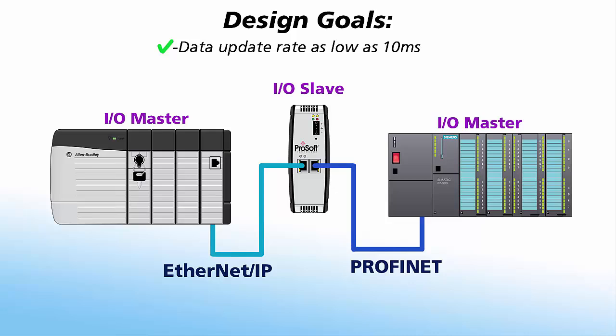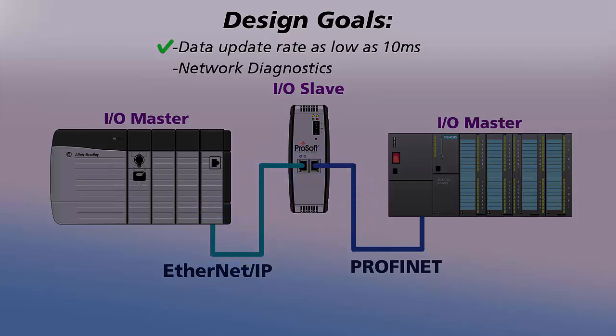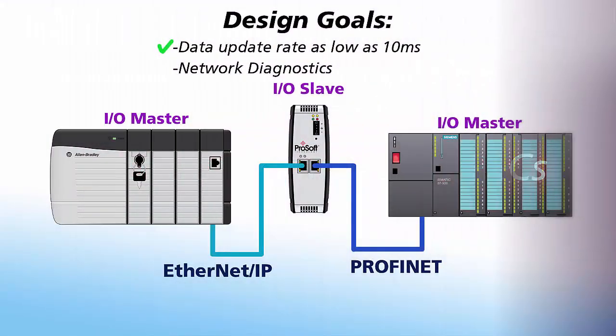We also need to be able to use the PLC programming software, or HMI, to view and troubleshoot communication issues. This method of communication is very deterministic and repeatable, thus offering very fast and precise timing. The data transfer rate is locked in by the program and I/O messages are given top priority by both PLCs. Using this communication method requires you to program both PLCs to set up the I/O messaging. This will also allow the PLCs to monitor the communication status of our gateway and display the diagnostic tags to an HMI or the PLC programming software.